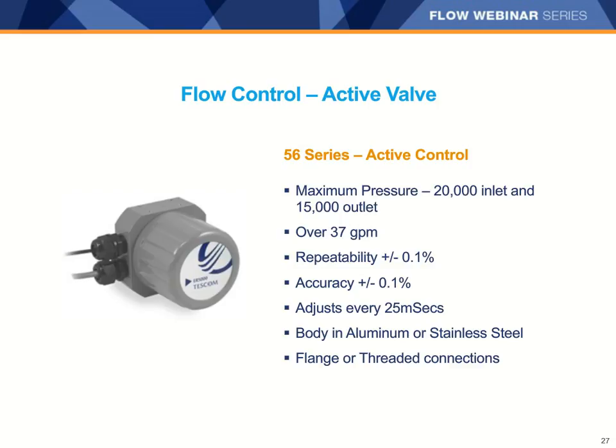The regulator will be specifically selected based on the pressure and required flow rates of the application and system. The PID controller itself has been used in many industries globally for well over 30 years and is really able to be tuned to any type of system configuration, any chemical injection skid configuration, or any plant or operator specific system. It can run remotely or be connected to a central control system if you need the feedback or want to change it remotely.